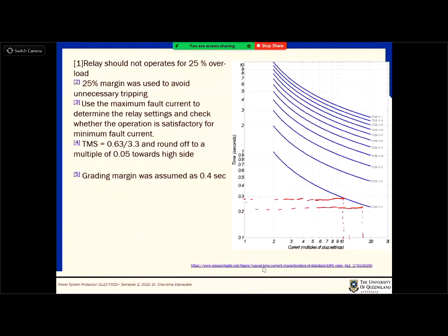So we need to look at the 0.6 operating time, where 0.6 is somewhere here. Do you agree that 0.6 is somewhere here? Along that line, the operating time of relay A should be above that. If it is below, the relay will operate faster than we think. It can be slower, because then there is no misoperation of relay 1 or relay A.